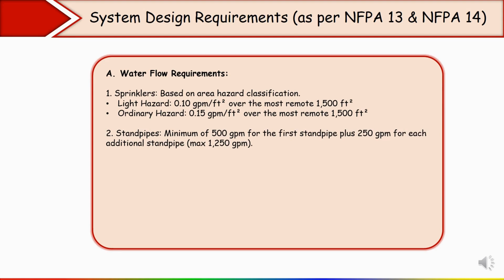And if it is a standpipe, the minimum is 500 GPM for the first standpipe plus 250 GPM for each additional standpipe. The maximum flow should be 1250 GPM, not more than that. Okay. Now if you see the pressure requirement, for sprinkler, the minimum we need is 7 psi at the most remote sprinkler head.